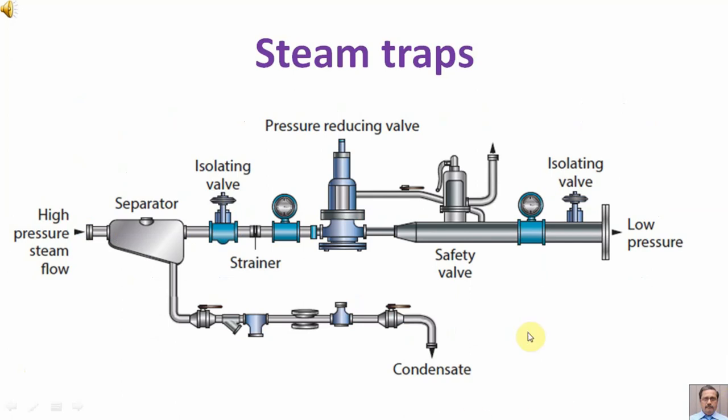In this diagram, we are showing a reducing station. It reduces high pressure steam into low pressure steam. It is having a safety valve, a pressure reducing valve, and separator. The function of the separator is to separate condensate formed in the steam line from steam.